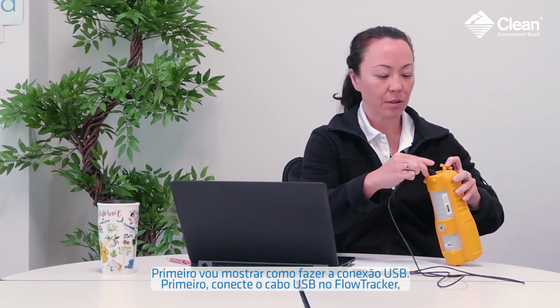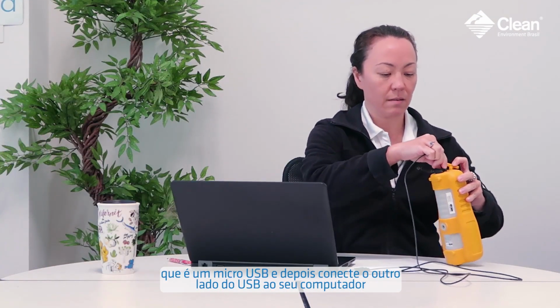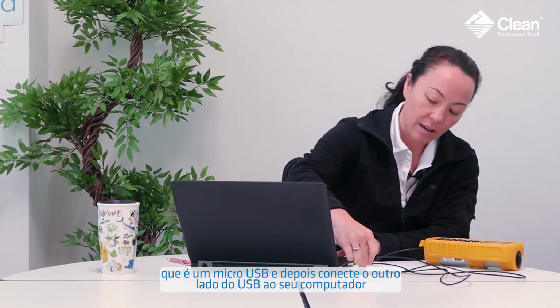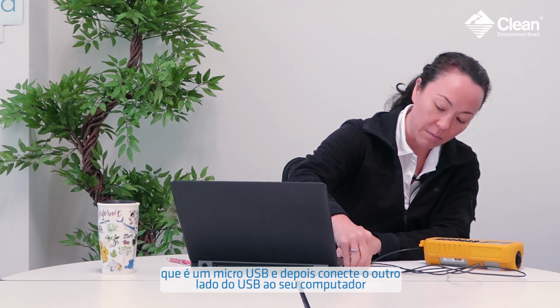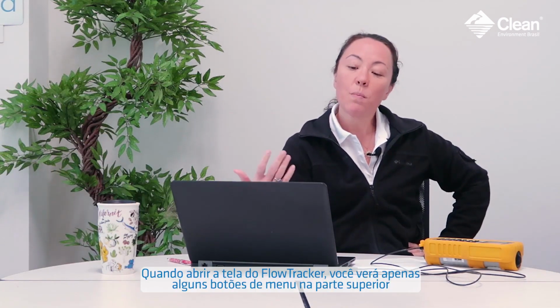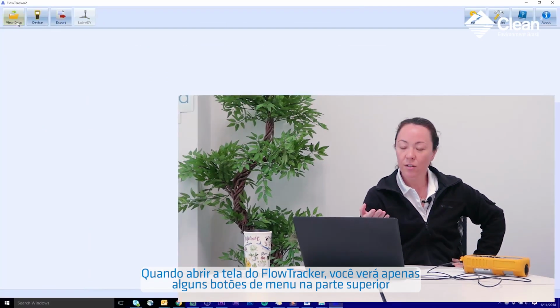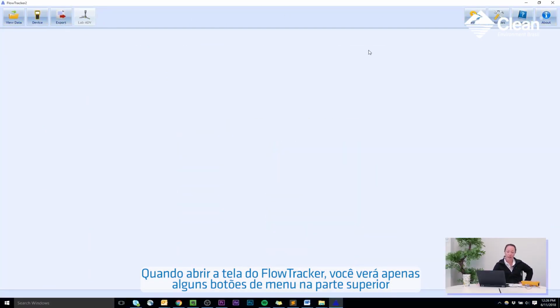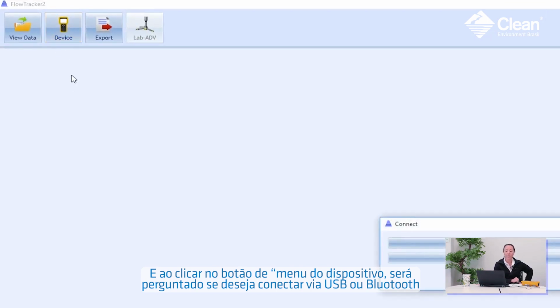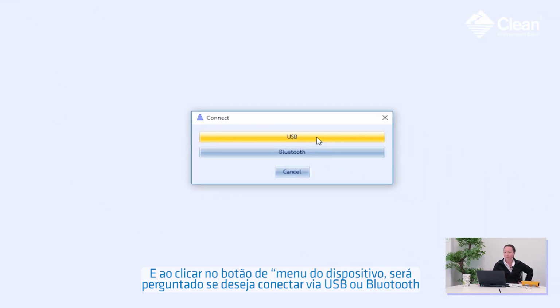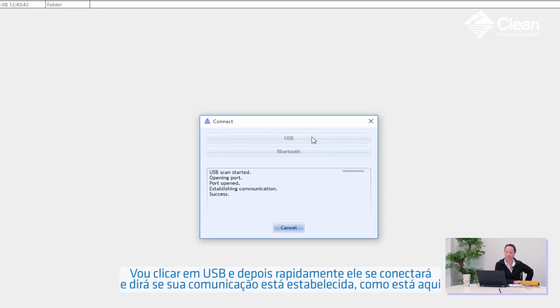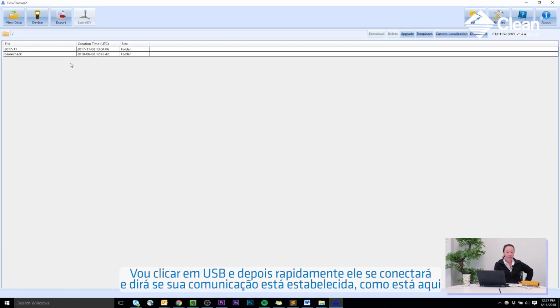First connect the USB cable to the FlowTracker, which is a micro USB. And then connect the other USB end to your computer. And then when you open the FlowTracker screen, you'll see just a few menu buttons across the top. And click on the device menu button. You'll be prompted, do you want to connect via USB or Bluetooth? I will click on USB. And then very quickly it will connect and tell you whether you've established communications, which I have.